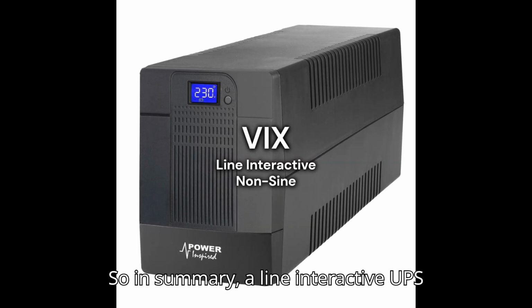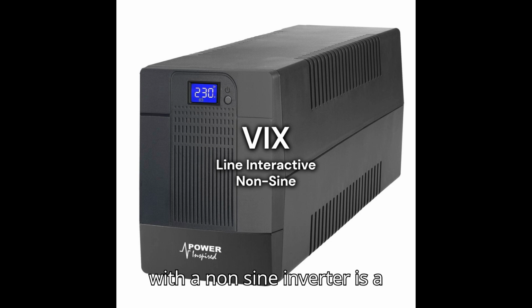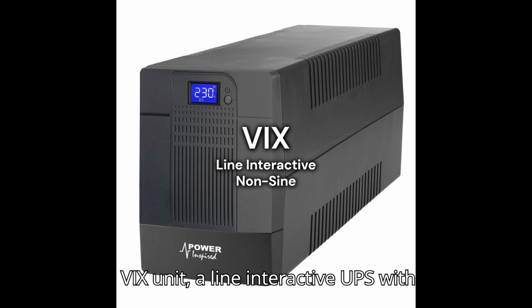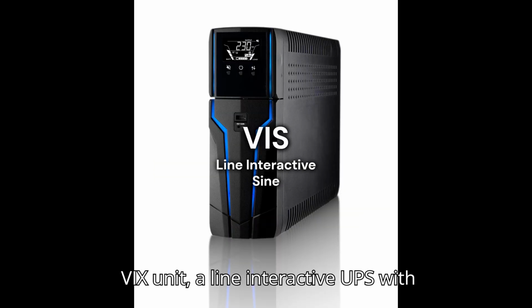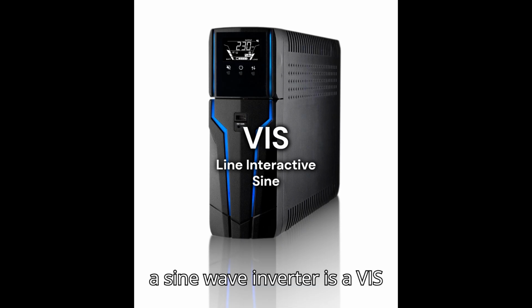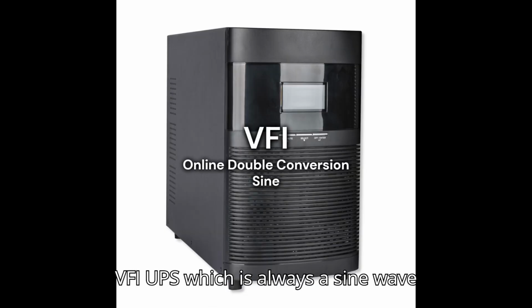So in summary, a line interactive UPS with a non-sine inverter is a VIX unit. A line interactive UPS with a sine wave inverter is a VIS unit. And an online unit is a VFI UPS, which is always a sine wave unit.